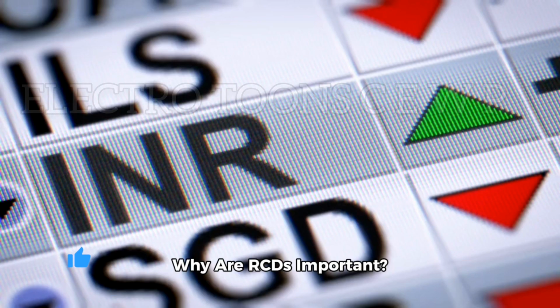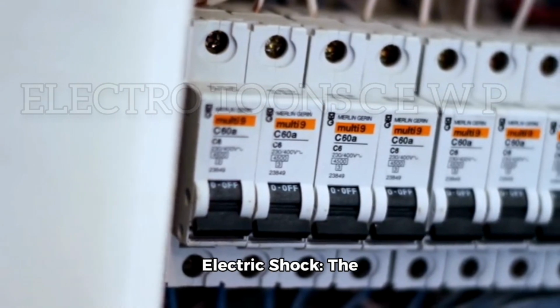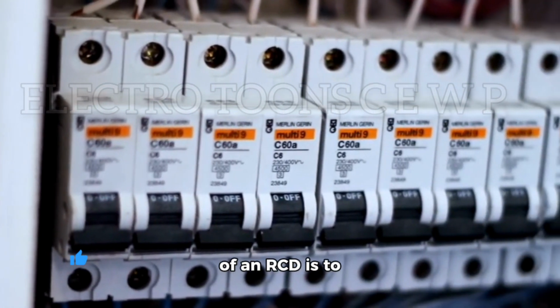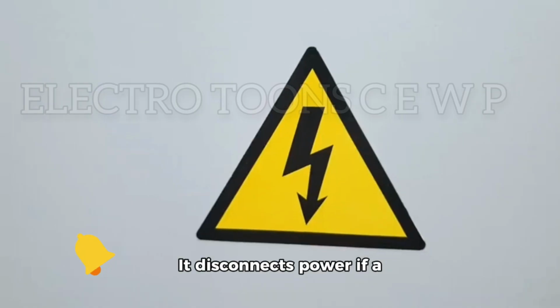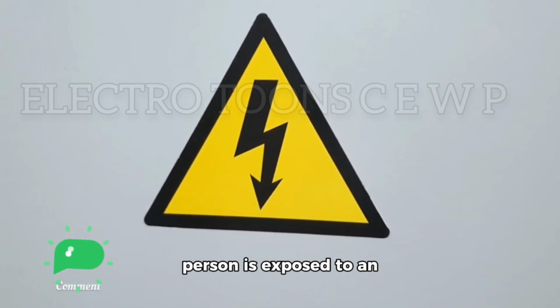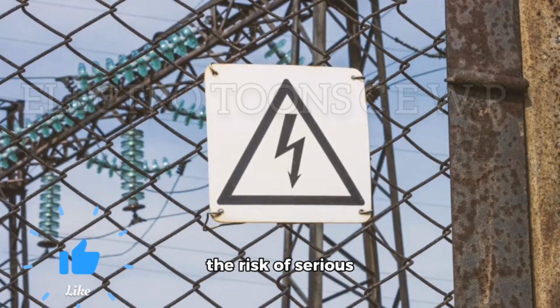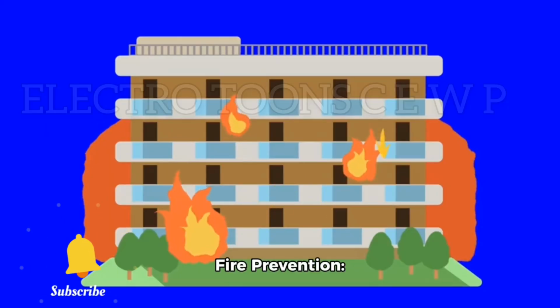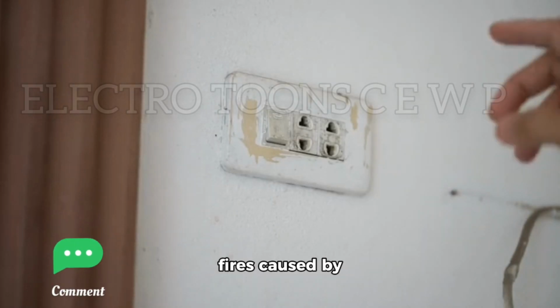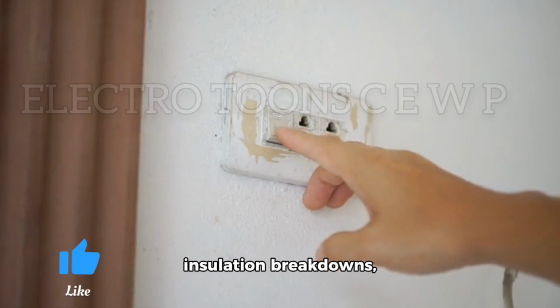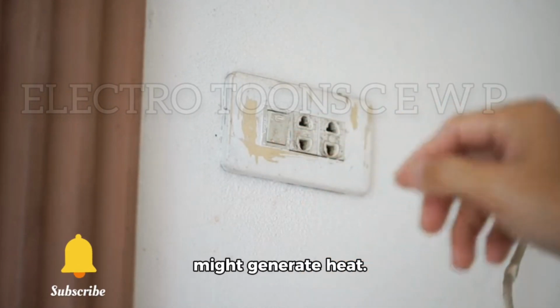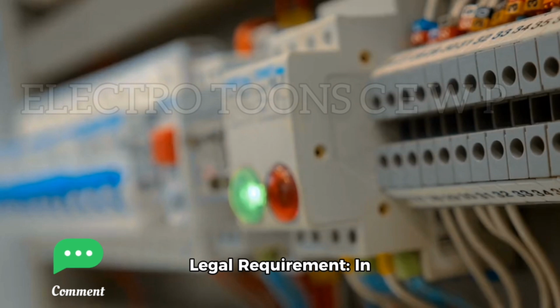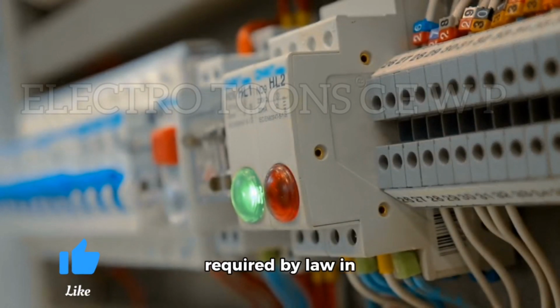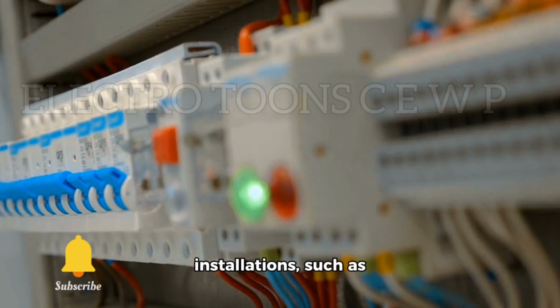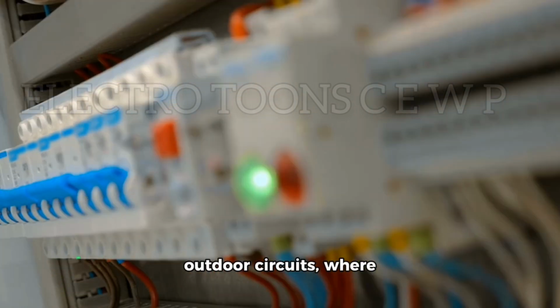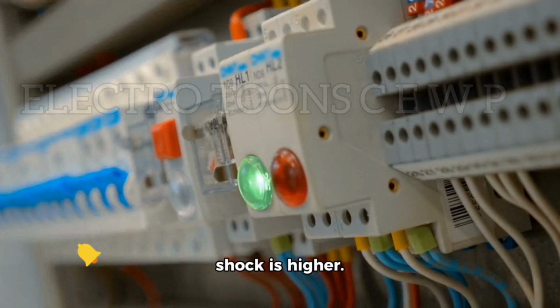Why are RCDs important? Protection against electric shock. The most important purpose of an RCD is to protect human life. It disconnects power if a person is exposed to an electric shock, reducing the risk of serious injury or death. Fire prevention. An RCD can also prevent fires caused by electrical faults or insulation breakdowns, where leakage current might generate heat. Legal requirement. In many countries, RCDs are required by law in certain electrical installations such as bathrooms, kitchens, and outdoor circuits where the risk of electrical shock is higher.